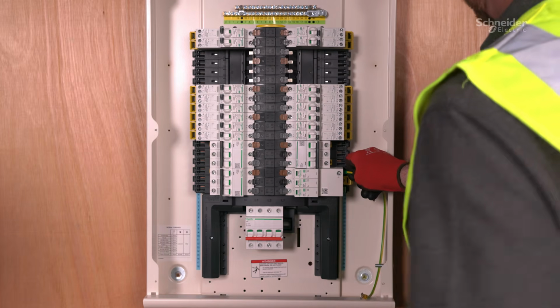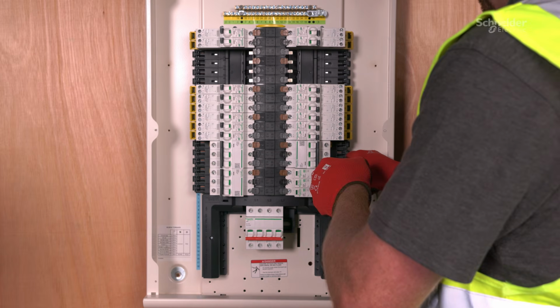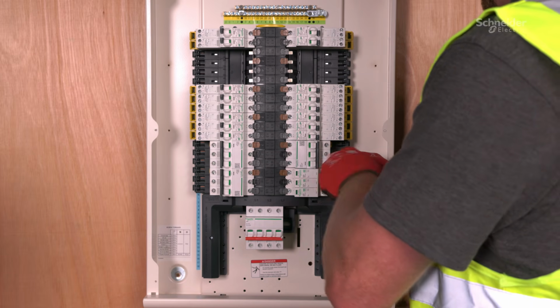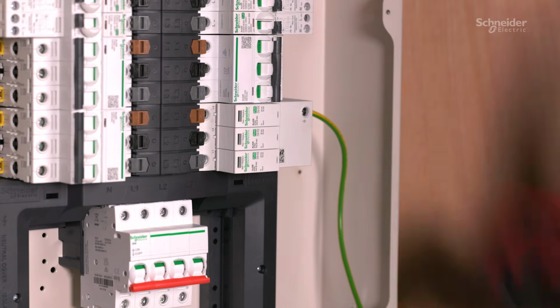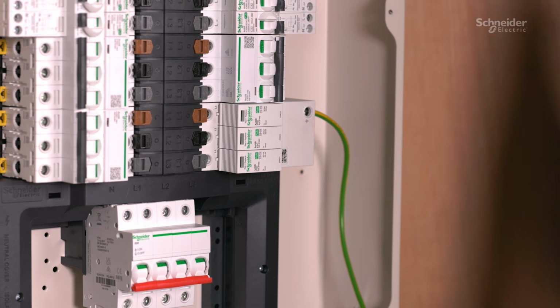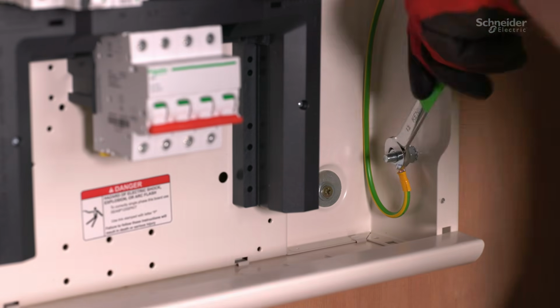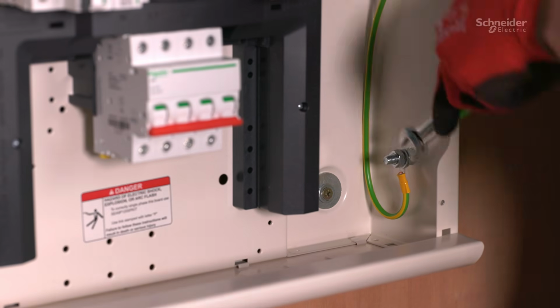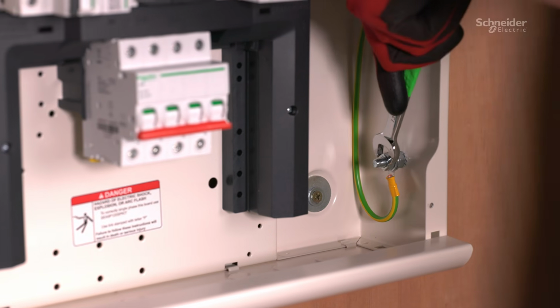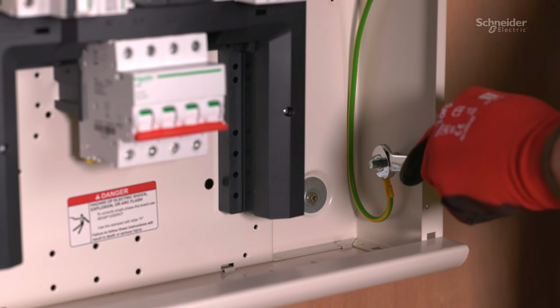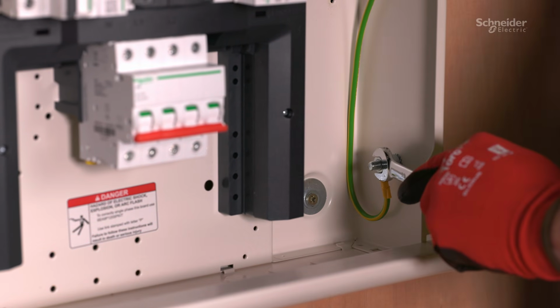Now the SPD is in place, we need to cable in the earth. For the earth, the cable needs to be as short as possible, and for this install we have already fitted an earthing bolt in the board for this. All of our Acti9 distribution boards come with these, and it's perfect when fitting your SPD.